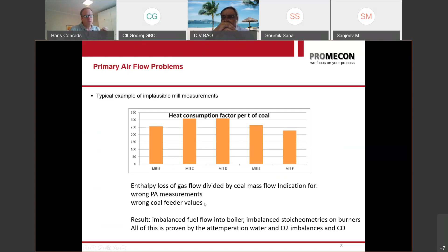And the reason for that is that you have most of them measured by delta pressure. You have a venturi, you have an impulse line, and you measure the delta pressure over your venturi. Why is that a problem? The problem is that the impulse lines start to clog with ash and dust. And over time, you will get a drift of your measurement. Now look at this brand new Alstom boiler in Germany. Look at the red line, which is the delta P indication, right?